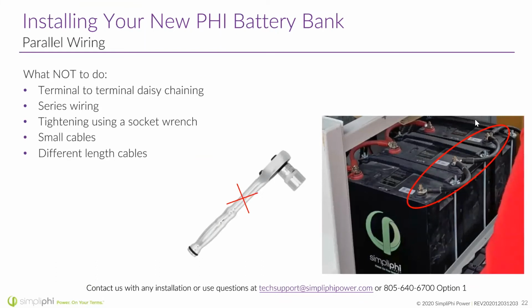Do not wire your battery bank the same way you had your lead acid bank. I know that daisy chaining is totally fine for most lead acid banks, but it is not okay for a lithium iron phosphate battery. It's going to cause imbalances. They're going to charge to different voltages. They're going to discharge at different amperages. They're not going to be well balanced. And for a battery that's going to last 10 years, you need to make sure this is very well balanced. We're not talking about a 2 to 5 year lifespan here like lead acid batteries.